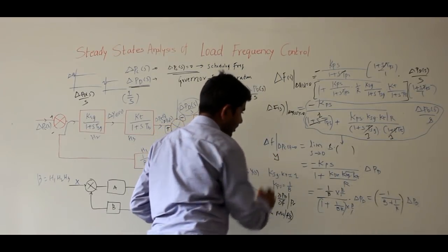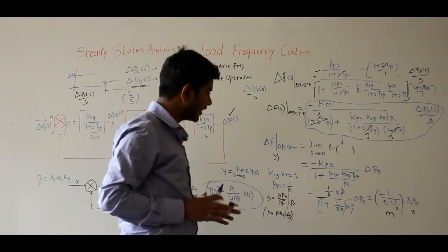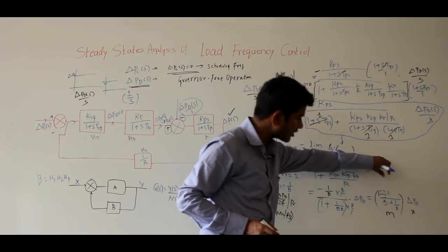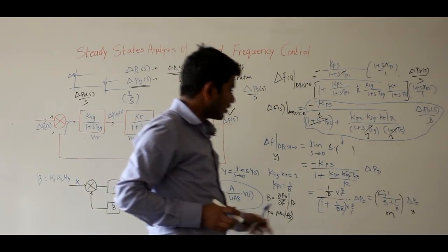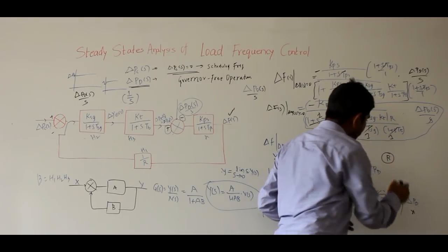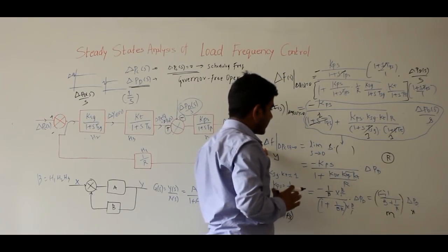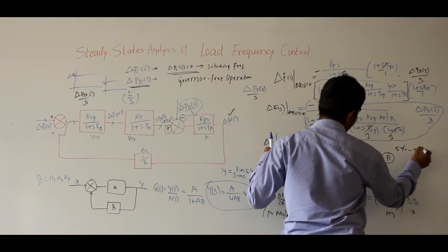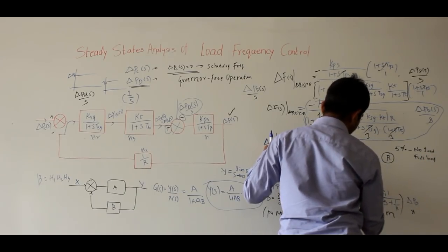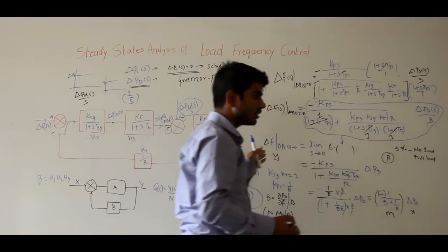So if I say this is Y, this is M and this is X, Y is equal to MX, you have a line equation, and you have a negative slope because the sign is negative here. This is just the droop, or the slope you can say. It has been observed that you can adjust R, the speed regulation of the governor, such that there are small changes in the frequency, that is the frequency change is just 5% from no load to full load.